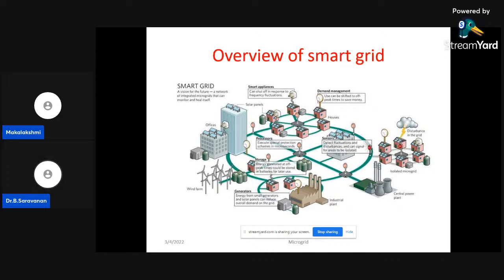Even if it is a hydro station, we can switch off for 15 minutes to half an hour, and within 15 minutes we can switch it back on. But for a thermal station, it's not possible. There are concepts called uptime and downtime, where you have to switch on if you want to go from normal water to a higher temperature. Normally the steam temperature is around 540 degrees centigrade in our national thermal power corporations. So if you want to raise the steam from normal water level to that, it takes a minimum of 8 hours. That's why it's not economical to switch off conventional power plants like thermal stations, nuclear stations, etc.